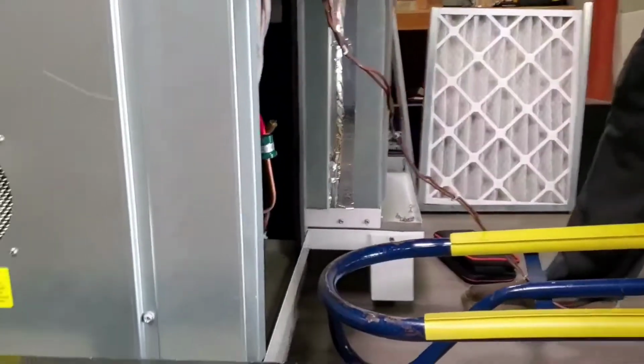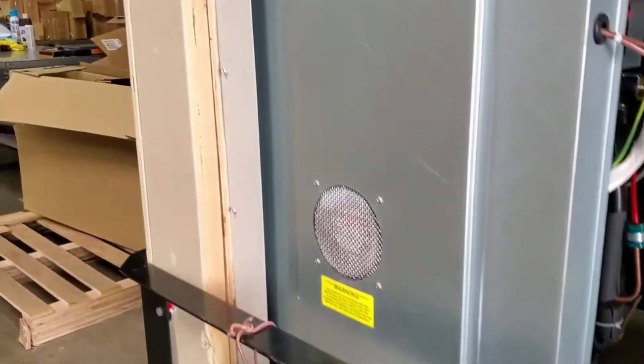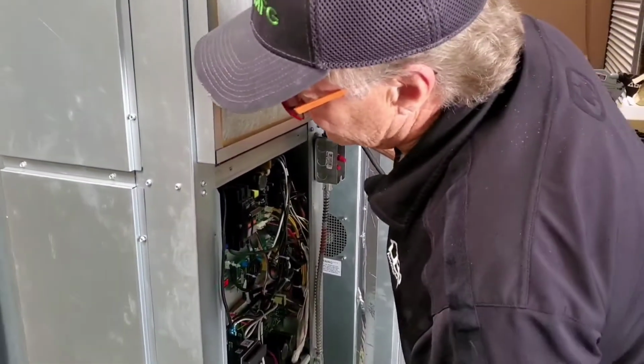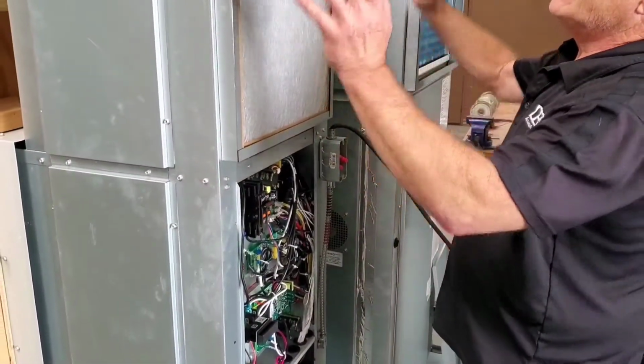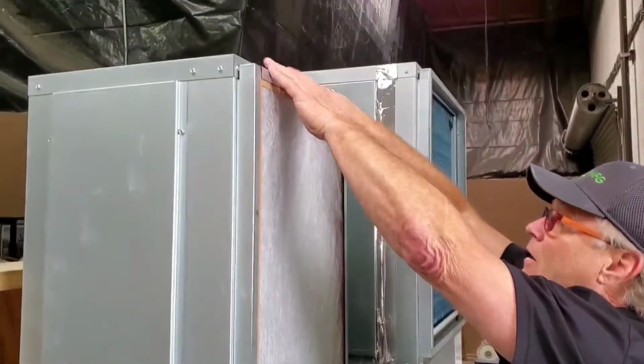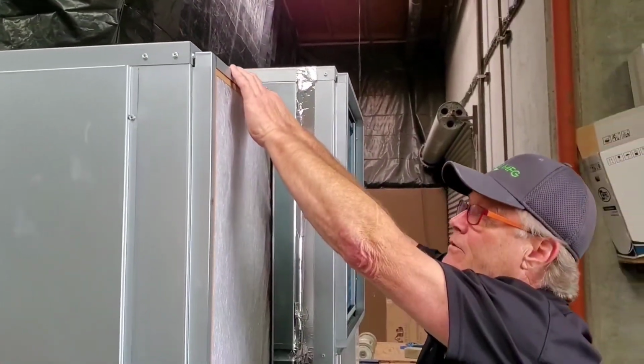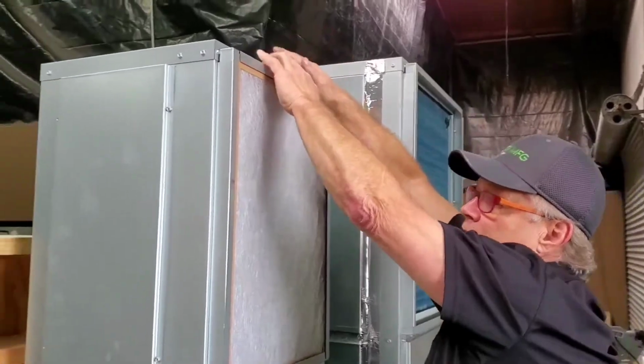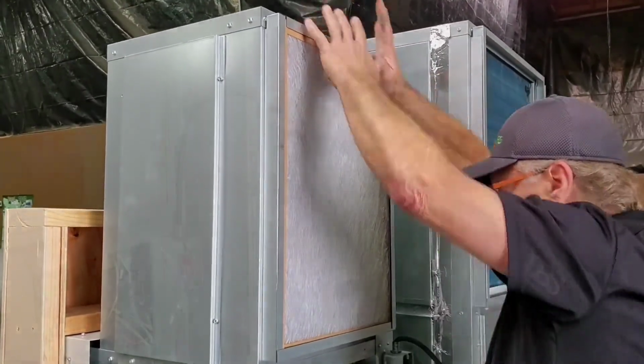Make sure the bottom down here all matches up, that you're plumb and you're in here all the way through. Check that gasket seal all the way around right before you go any further, because if you need to get in there and seal it with silicone, now is the time to do it. Okay, then you'll replace your supply duct on top. Ours is just a plenum with a grill, so we'll leave that off. Screw it back down, tape it down however it was refastened.